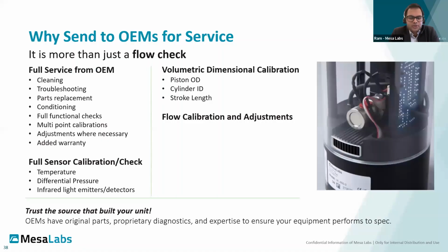When you send your equipment or instruments back to OEMs for service, the objective is straightforward: restore it back to its original performance. OEMs built the product, so a trusted source had built the unit. So this goes beyond just basic flow checks. OEMs will ensure that devices are cleaned, tested, and recalibrated as a complete system. Sensors are verified, components are replaced, and any required adjustments are made to bring the unit back to published specifications.